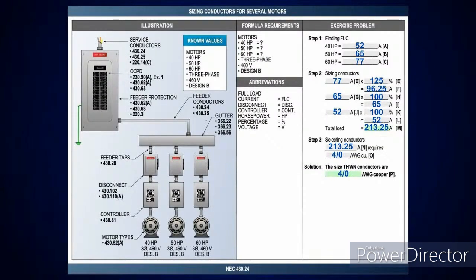All right. Then if you've got multiple motors, you heard me talk about this last week. I said you take the largest motor at 125%, everything else is at 100%. We kept it pretty easy so you could go find everything. You've got a 40, 50, 60 horsepower motor, it's 460 volts, and it's three phase. Pick up the 460 volts, come across: a 40 horsepower is good for 52 amps. A 50 horsepower is good for 65, and a 60 horsepower is good for 77. Naturally, the 60 horsepower is the largest, so we're going to take that 77 amps at 125%. It'll give you 96.25 amps.